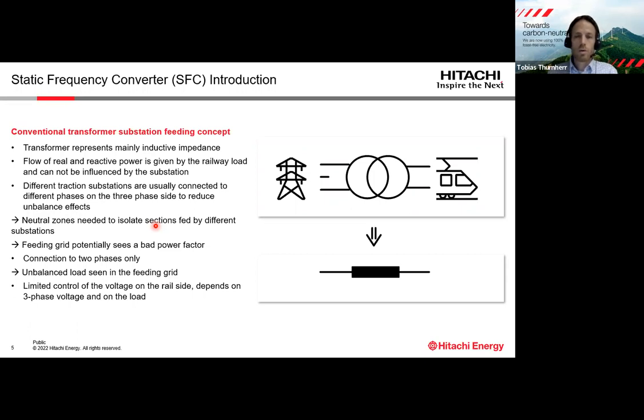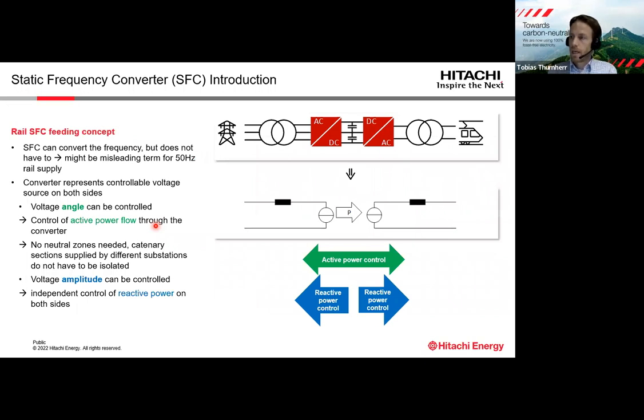One option to reduce this voltage unbalance is to connect the substation to a very strong grid with a small short circuit impedance or a high short circuit power, and this is the case for high voltage grids. So typically a transformer rail substation is connected to a high voltage grid. And then with a transformer, we have only very limited control of the voltage on the rail side, and the voltage on the catenary also depends on the 3-phase voltage and on the load. I say limited control: there can be tap changes introduced, but they are not very fast, and if operated frequently, they need maintenance.